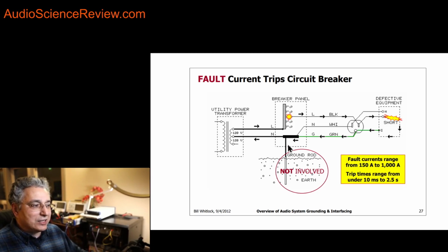This ground rod is in here in case of a lightning strike to the wiring that's upstream of your transformer and your feed. Should that hit there, there's a path in here that will bring it down to ground because those poles also are grounded. So some of that energy gets shunted down, and I've covered surge protectors and things later on, but that's the only thing this thing is supposed to do, is deal with these surges from lightning strikes externally coming in here. This ground rod that's outside of your home plays no role either in normal operation of your system or in the event that this is shorted out. Okay?